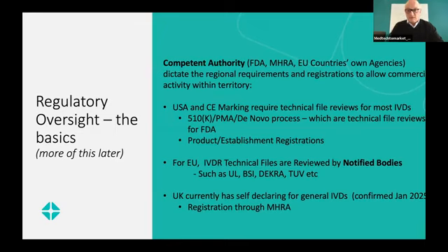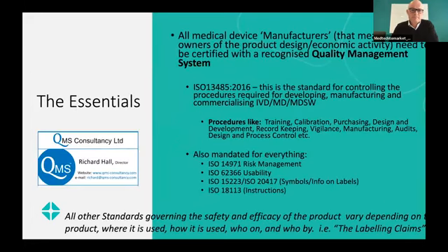In order for Europe to do that technical file review, the MHRA don't necessarily do that. They use notified bodies, and these are companies that specialize in reviewing the technical files. So this could be BSI, DEKRA, TUV, UL, whatever. And there's about, I think, 10 or 12 of them throughout Europe that will do technical file reviews for diagnostics. In the UK currently, as of January this year, for most diagnostics, not all, are self-declaring under the general classification rule. So that's a slightly different, just a registration process.